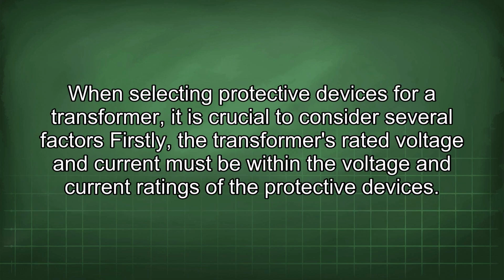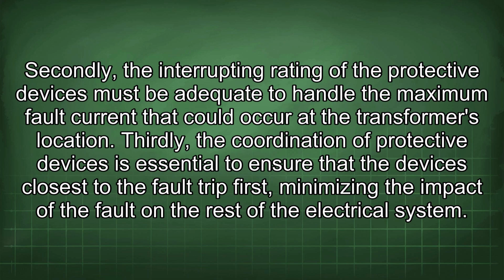When selecting protective devices for a transformer, it is crucial to consider several factors. Firstly, the transformer's rated voltage and current must be within the voltage and current ratings of the protective devices. Secondly, the interrupting rating of the protective devices must be adequate to handle the maximum fault current that could occur at the transformer's location. Thirdly, the coordination of protective devices is essential to ensure that the devices closest to the fault trip first, minimizing the impact of the fault on the rest of the electrical system.